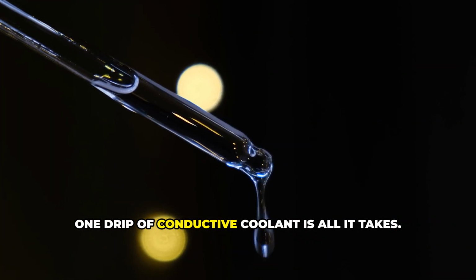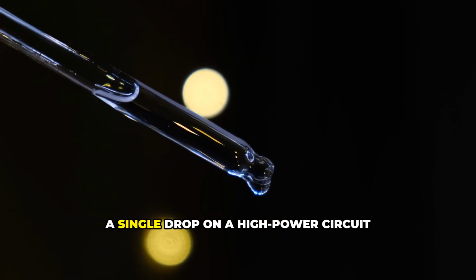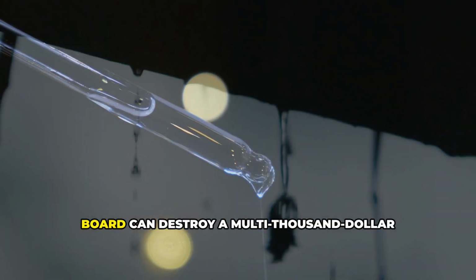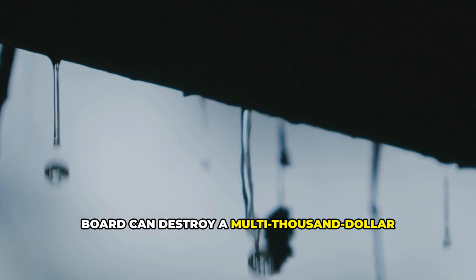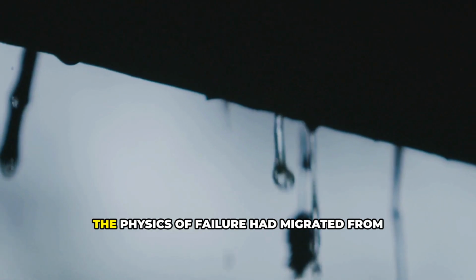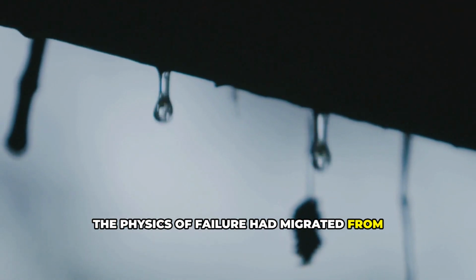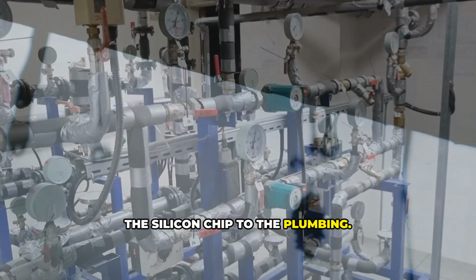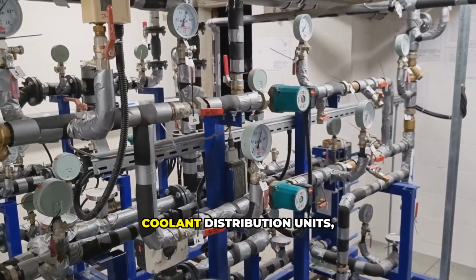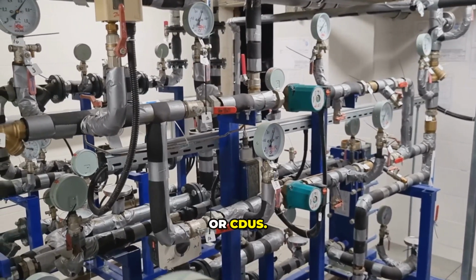One drip of conductive coolant is all it takes. A single drop on a high-power circuit board can destroy a multi-thousand-dollar GPU node, and worse, trigger a cascading shutdown of an entire rack. The physics of failure had migrated from the silicon chip to the plumbing. At the center of this crisis are the coolant distribution units, or CDUs.